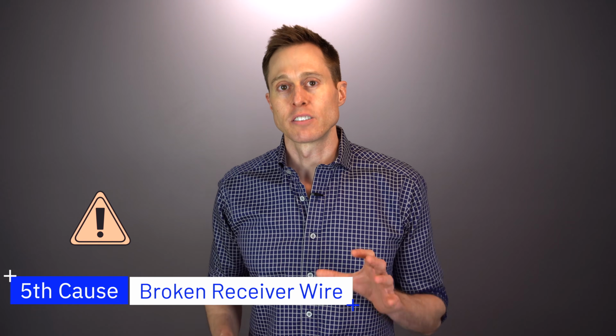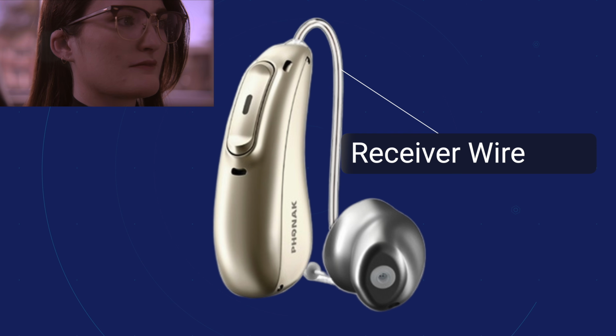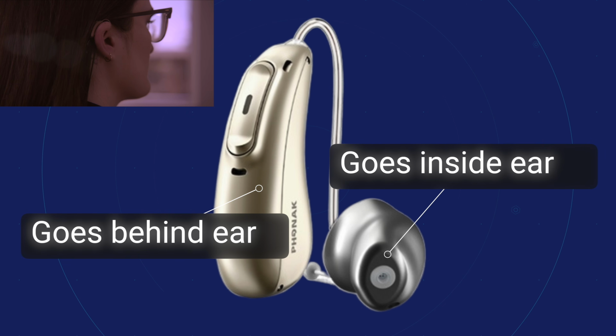Since most hearing aids dispensed today are receiver in canal style devices, there is a high likelihood that if your hearing aids are malfunctioning, it's because of the receiver wires, especially if your devices are several years old. The receiver wire is what takes processed sound from the hearing aid that's behind your ears and sends it to the speaker or receiver that's inside of your ear canal.